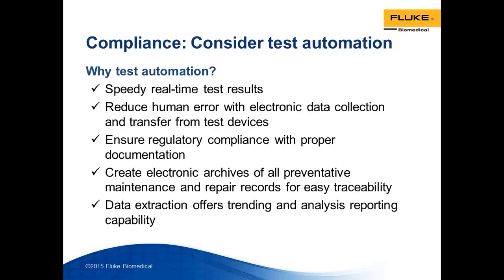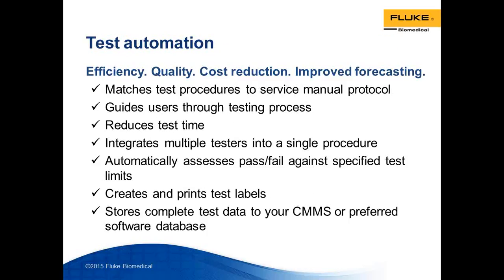It's also very important when looking at predicting failures in the future. So there are definite advantages, but the biggest advantage of test automation, if you ask me, is compliance, because in test automation you are essentially creating a template. That template reflects the exact same steps that the manufacturer or your organization requires for testing each infusion pump. And because you prescribe that test and guide the user through that process, not only do you reduce the ultimate test time, but you're also getting a pass or fail immediately with every single test.